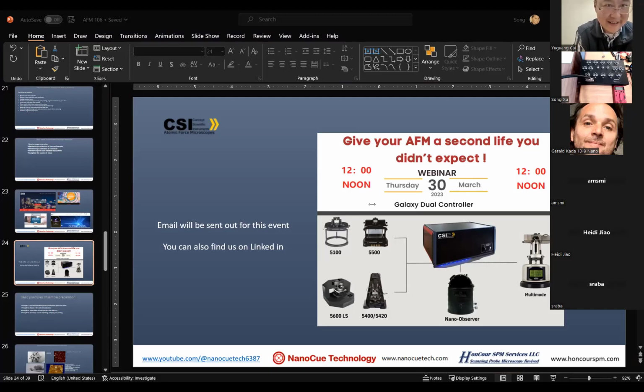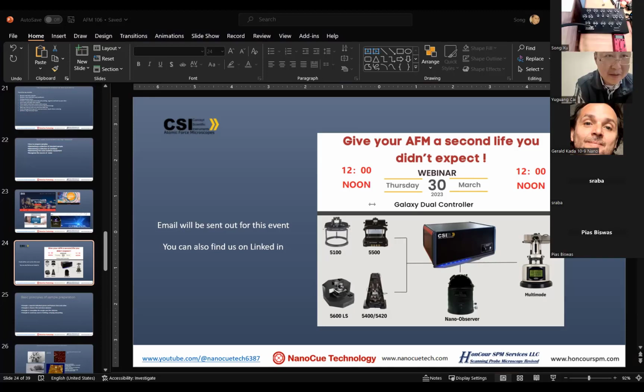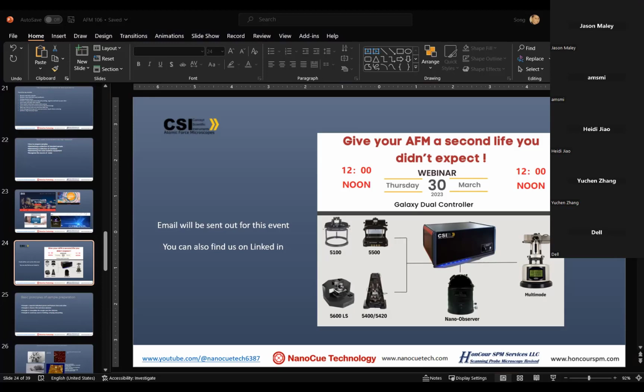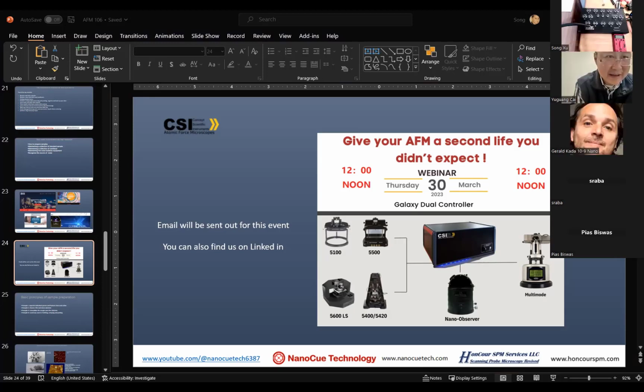Okay, that tells me you probably have two different series of systems. One system was produced years and years ago that had a 4.3 times gain in the head electronics box. So if you have that 4.3 times difference, and you said it's roughly 5 times, that's probably because you have two different revisions. Trust your software. Okay, the software is okay. Yes. Now, for the one that's only a few millivolts or tens of millivolts, it's ideal that you came to this conference, because this is where we're going to talk about why you have that difference. That's all in the calibration of your controller. So my take-home message for both systems is to trust the software? Yes. Based on the limited knowledge that I have of your particular operating setup, yes, I would trust the software.